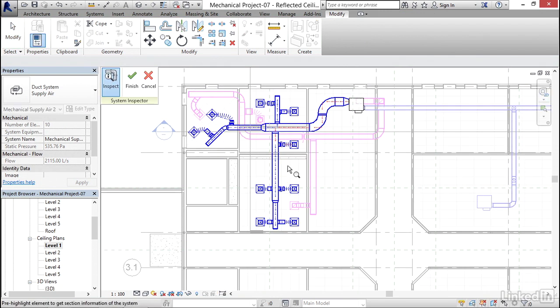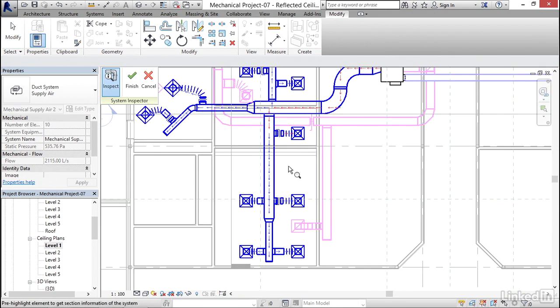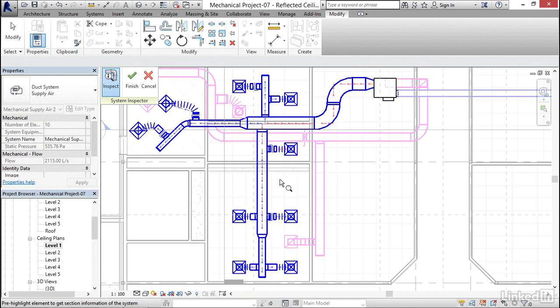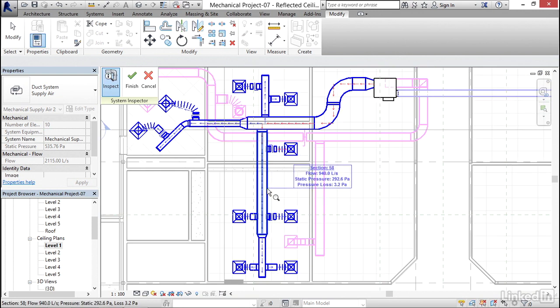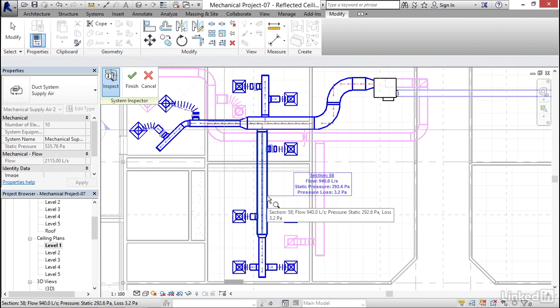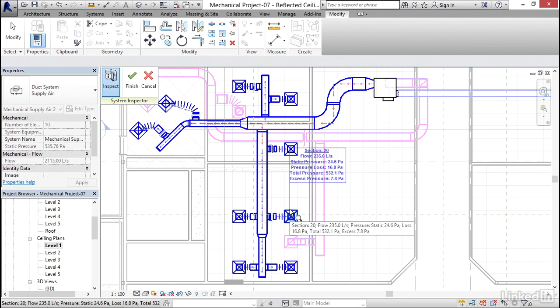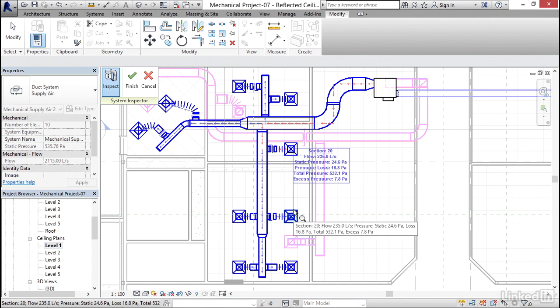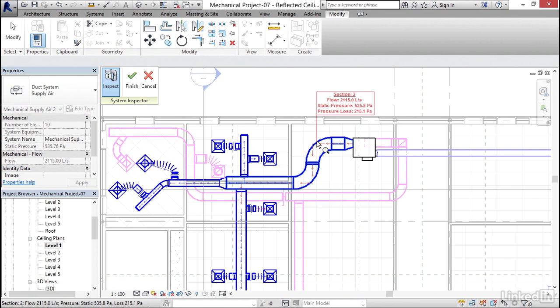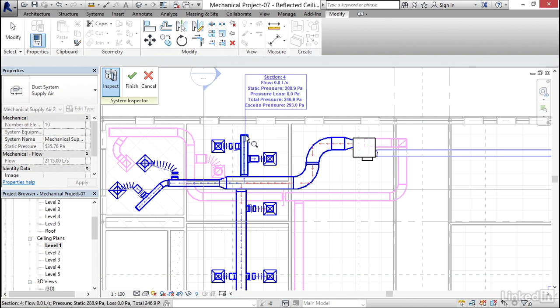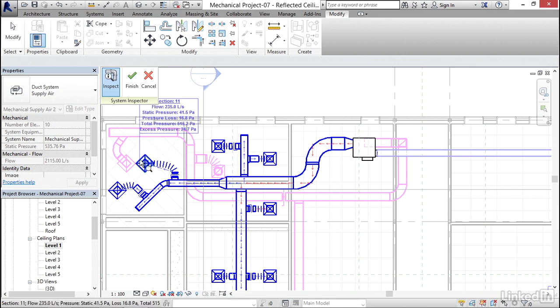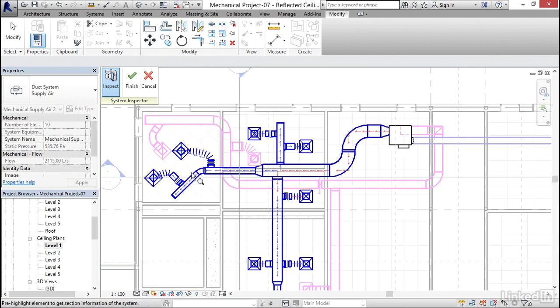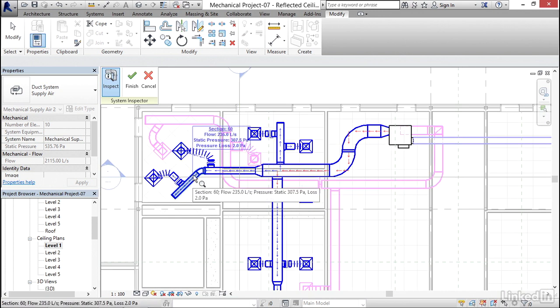Now basically what I can do is we have our flow arrows, so I'm going to hover over one of these items, and it gives us our flow, static pressure, and our pressure loss. We can go over a diffuser. It shows us what our CFM is. We can come over here and look at this one, static pressure. So this is going to give us any errors that we may have. I can just kind of go through and inspect my entire system.